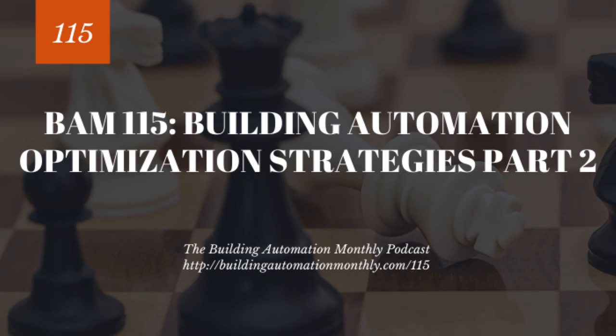Now, that was a lot to take in. I realized that was a deep concept. So let's revisit that real quick. Okay. So you have these VAV boxes, and these VAV boxes have three ways of saying that they're calling for cooling. One is the difference between space temperature and space temperature set point. The other is the damper position being greater than a certain percentage. And the third is calculating the average of the damper positions.